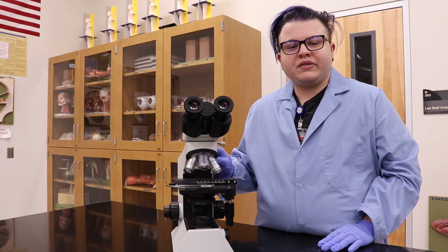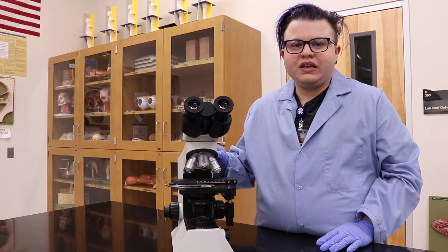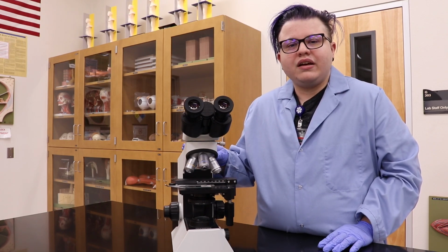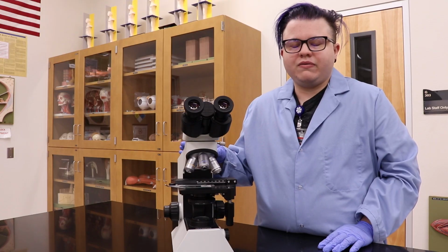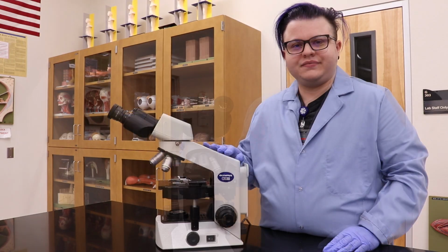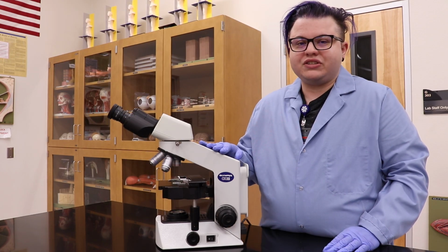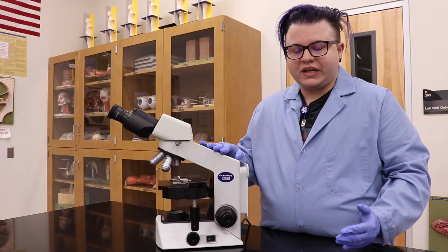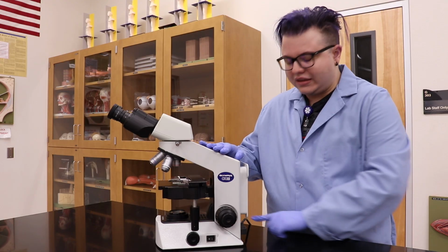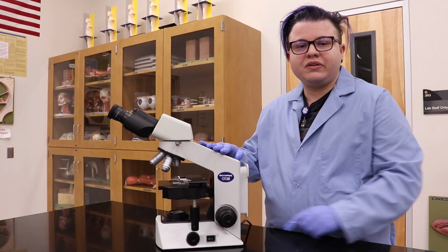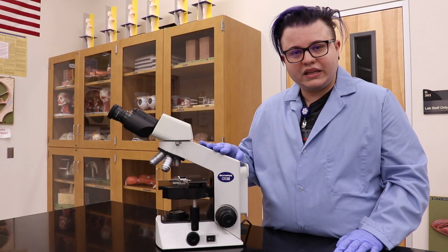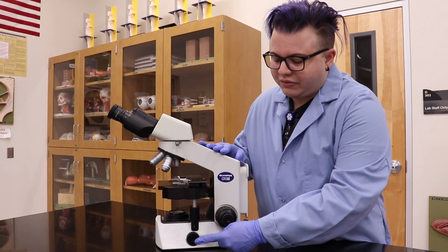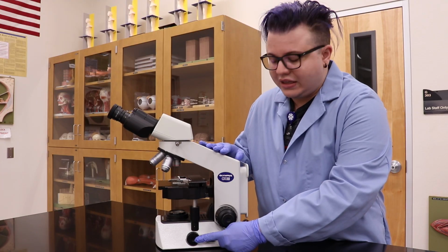The next section we'll be going into is troubleshooting. There are a couple things that you can look at when your microscope isn't working before you bring it to your instructor. If your microscope isn't turning on or the light isn't showing up, some things you can check are that the power cord is plugged in and into an outlet that is working correctly, or that the rheostat is turned up.